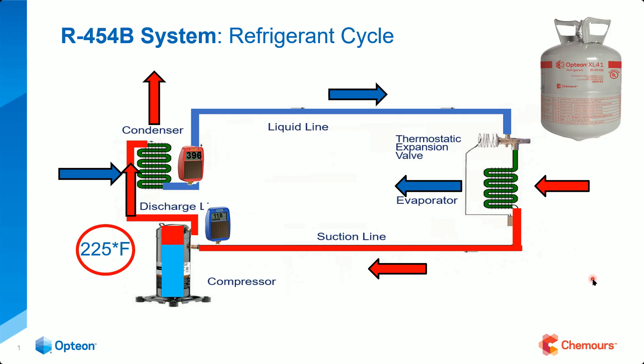I used 454B as the refrigerant and even put the gauges on for you. When taking subcooling, some manufacturers ask that you take pressure and temperature within six inches of each other — Copeland usually recommends that, though it's not set in stone if it's not possible. On a residential unit, line sets might only be around 35 feet. I like taking subcooling here because I want to make sure we have a full line of liquid going into our metering device. Any saturation or air bubbles and you don't have a full column of liquid — you have an inefficient system.